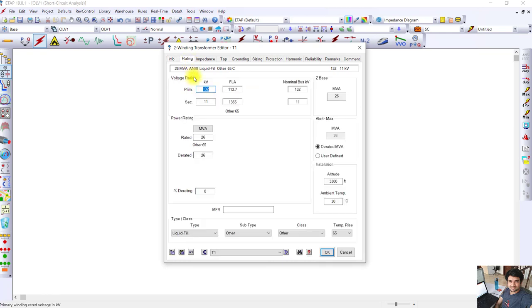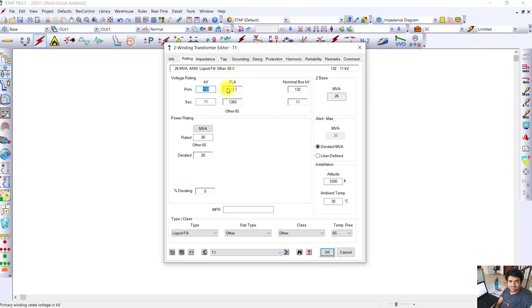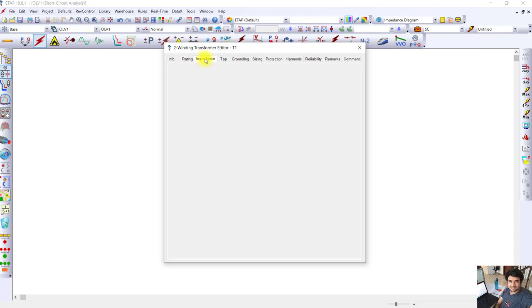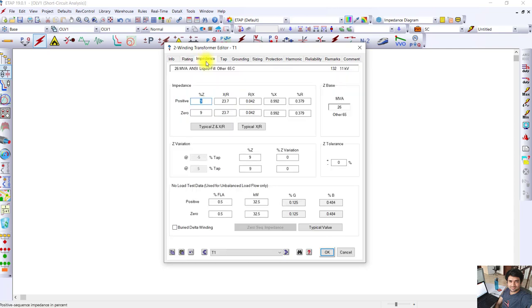The full load amperes FLA at the primary side is 113.7 and the secondary is 1365 amperes. Impedance of the transformer is 9 percent. The impedance of 132 kV/11 kV transformer varies from 9 to 12 percent.